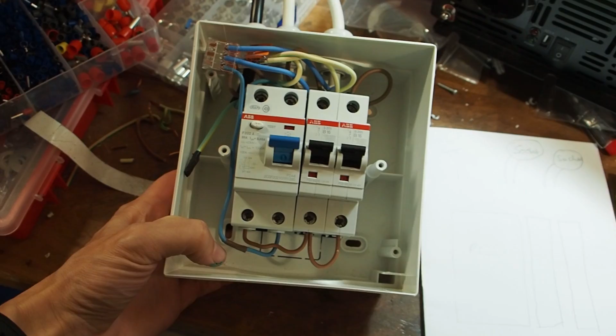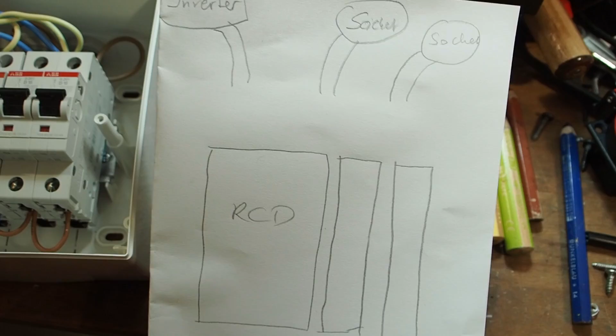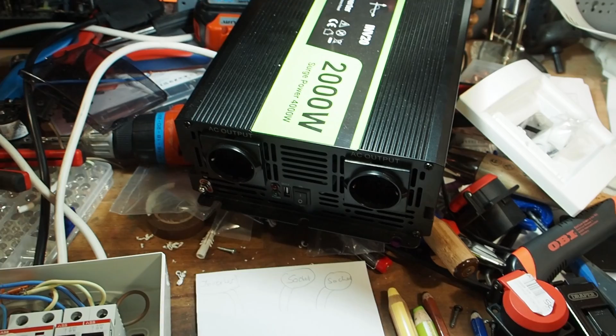Okay, I've just wired my breaker box and it looks like this. It looks a little complicated, so I'm going to explain it with this drawing here. The network coming from inverters is an IT network, which is a little different from the one you're used to in general households. The problem is that the phase and neutral are not really defined, and you're also not getting a true ground from an inverter. So we have to make a ground, and we have to change the network from IT to TN, and only this way is the RCD going to work.